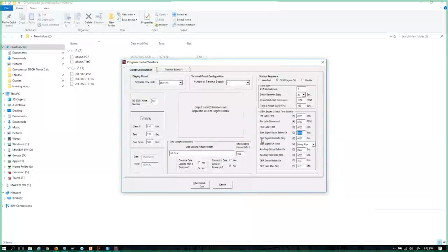Now, start signal hold after stop. Some OEM systems are different from the others. Some OEM systems, this needs to be 0, such as Waukesha. Caterpillar, we want to have at least a 1 second delay on their OEM systems. Start signal on time. Again, on Caterpillar engines, this would remain on. Once we initiate the start signal, we keep it on the whole time during the run process. But if it was a Waukesha, say with an ESM system, we would pulse it for 2 seconds and then turn it off. All the Waukesha wants is just a pulse signal. So we have those options.